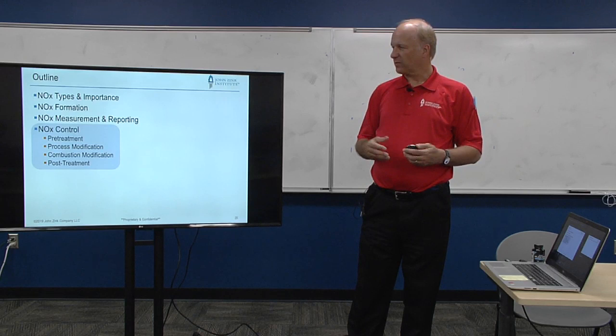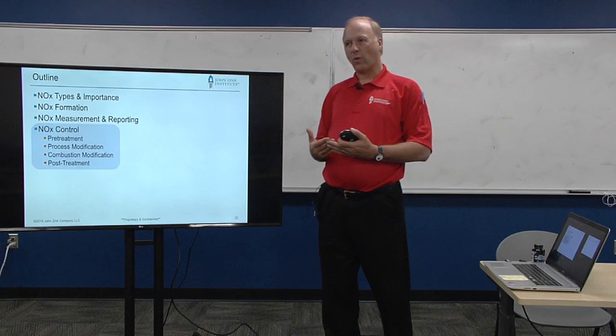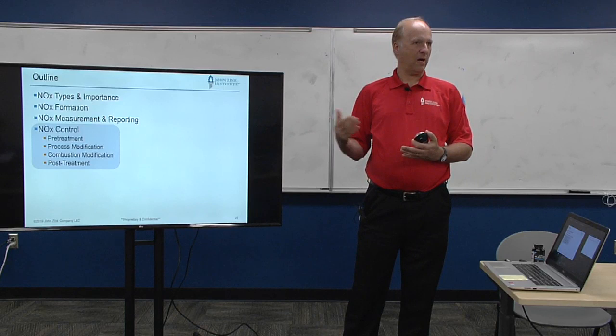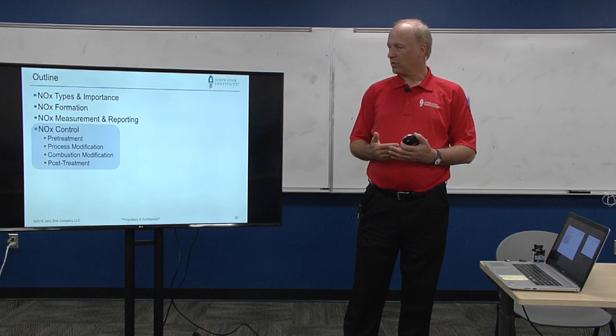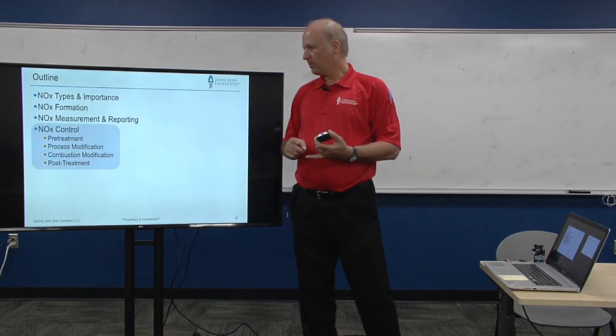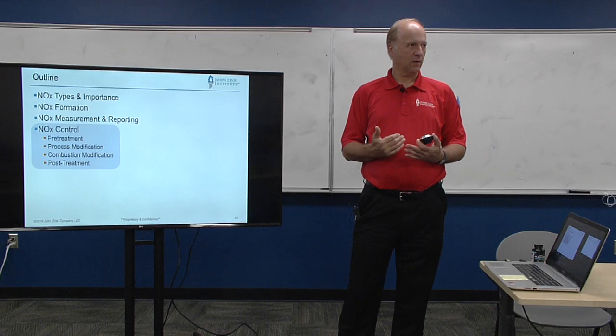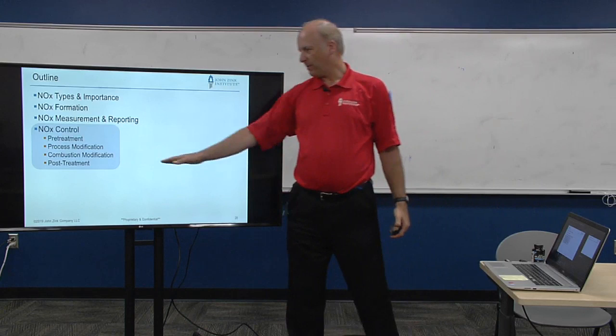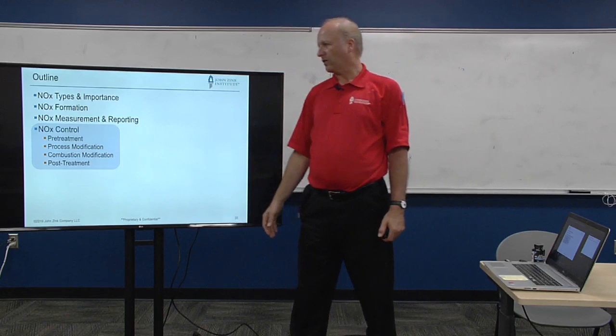The last topic for today — and where we'll spend most of our time — is how to minimize NOx. There are four general ways of reducing pollution: pre-treatment, process modification, combustion modification, and post-treatment. I'll give examples of all four for NOx, but we're going to spend by far the most time on combustion modification — what can we do to the burners to reduce NOx?